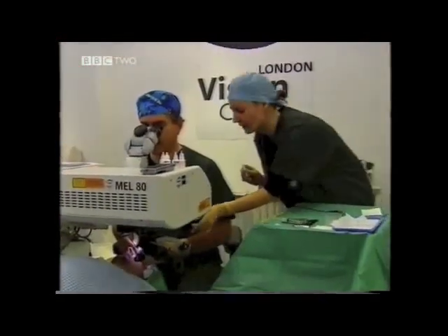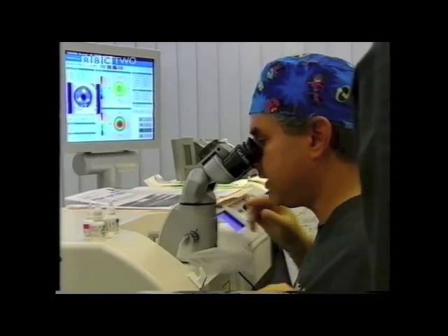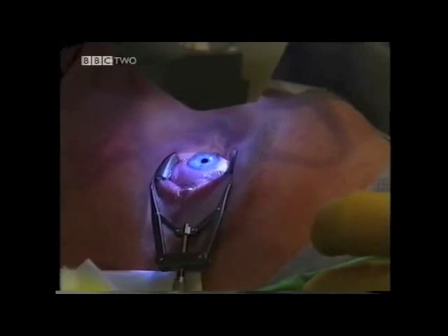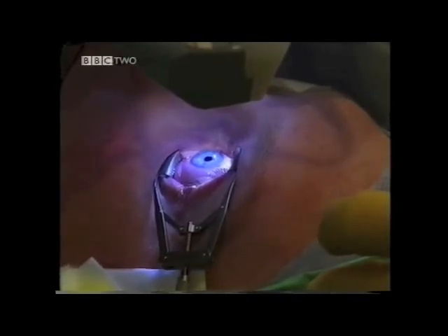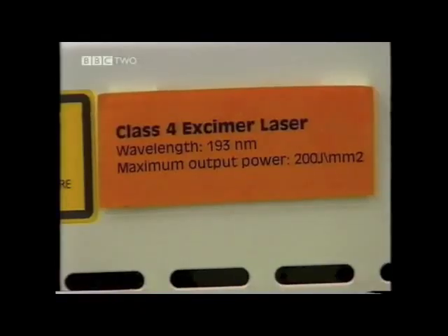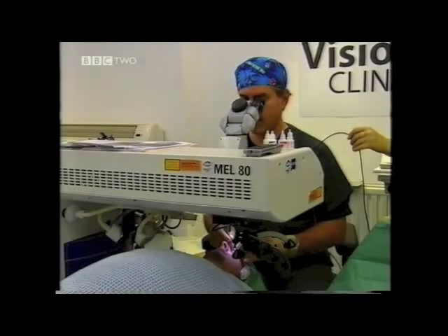One extraordinary use of ultraviolet light is in laser eye surgery, where the cornea is reshaped painlessly to improve eyesight. The amazing thing about ultraviolet light at 193 nanometers, which is the frequency that we use, is that it is completely absorbed by corneal tissue. Cornea is the window at the front of the eye, the watch glass, if you like, through which light passes. The advantage of all this energy being absorbed into this very small area of the surface is that every time the laser pulses, that energy is absorbed, and only in the order of 1/4 of 1,000th of a millimeter of tissue is removed per pulse.